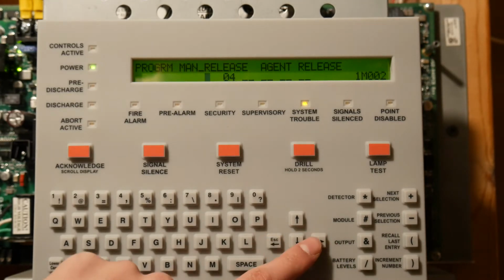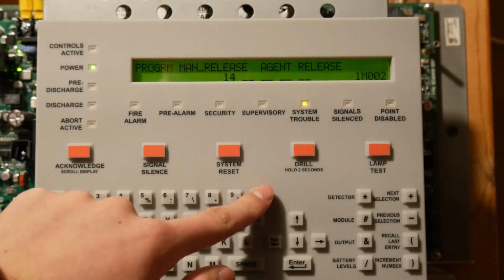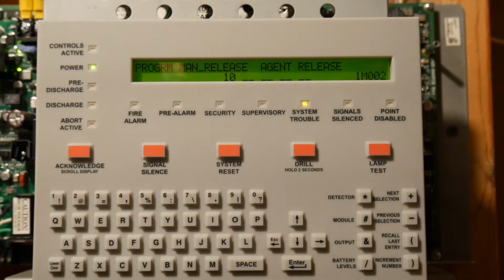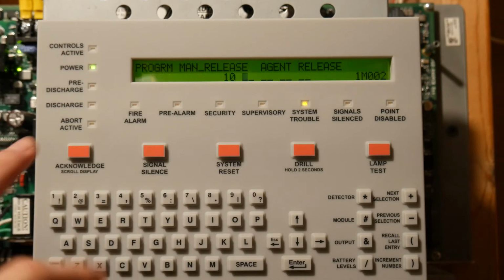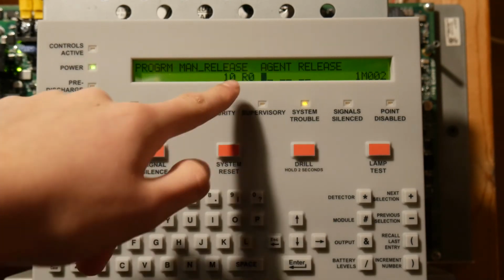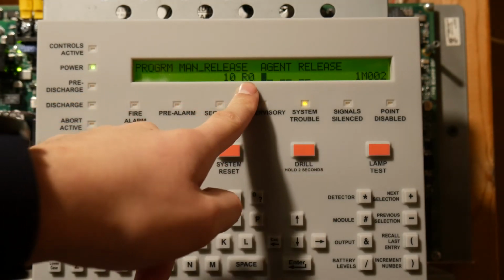I'm hoping I spelled that right because I don't know how to spell. And with agent release zones, it's a bit different. So we're going to set this as zone 10 because I do not want this to activate the fire alarm NACs, I just want it to activate its own NAC. So we're going to set this as zone 10 and mark it as a releasing zone. So this is going to activate releasing zone 0.